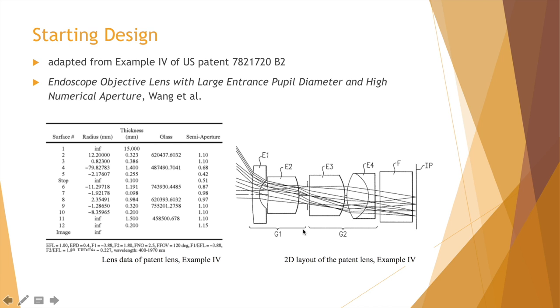In order to correct chromatic aberration, the two elements in the doublet lens have refractive indices differing by more than 0.02 and the Abbe number differing by more than 15. An optical filter is also placed in between the last lens element and the image plane.